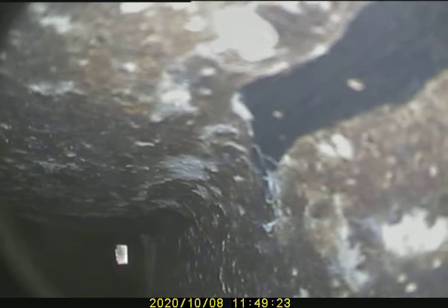So what's that right there? Looks like a nice hole — you've got a hole in the flue. Actually, it just gives that illusion. You have a lot of deterioration around it though. It's definitely an optical illusion. There's a ton of deterioration in this thing. Sulfur really just beat this tile up.